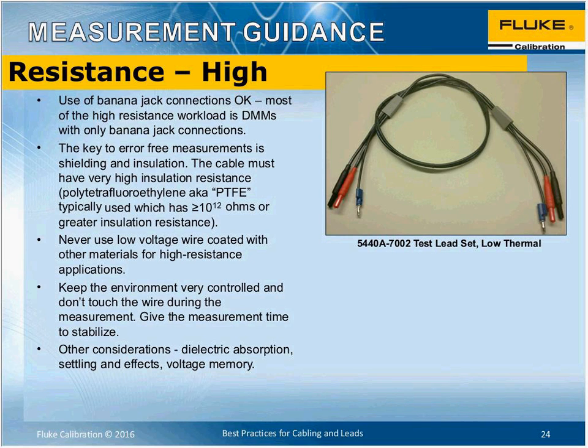High resistance is so much different than low resistance. This is one area where we would want to use a larger cable, typically a banana plug. The reason for a banana plug in this case is that the DMMs being tested typically do not have a spade lug connection, so it's acceptable to use these types of cables. One thing you're going to want is that the cable must have very high insulation resistance. Some call it PTFE, an abbreviation for a very long word that I'm not going to embarrass myself trying to pronounce. But basically, you want a cable that has greater than 10 to the 12th ohms of insulation resistance. Don't use low voltage wire coated with other materials for high resistance applications.